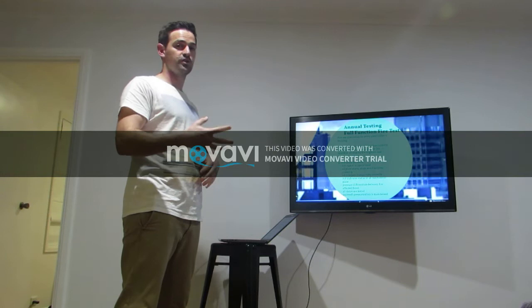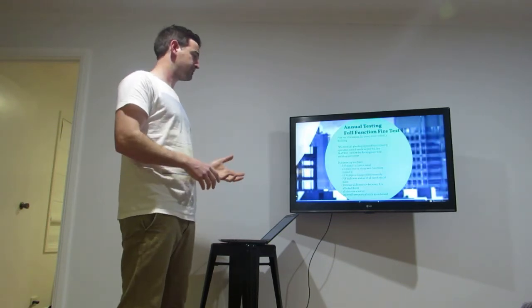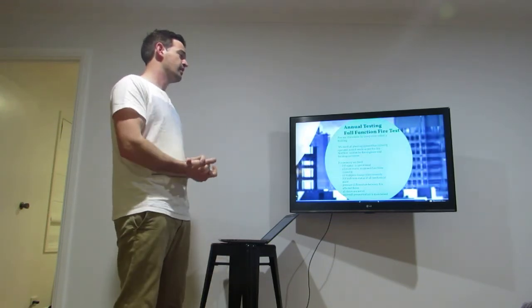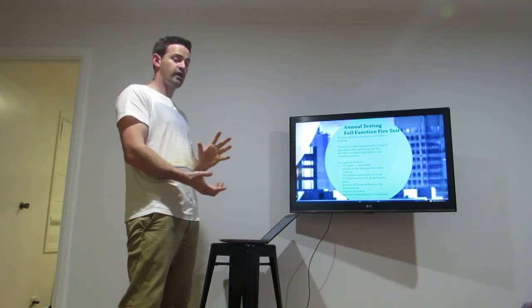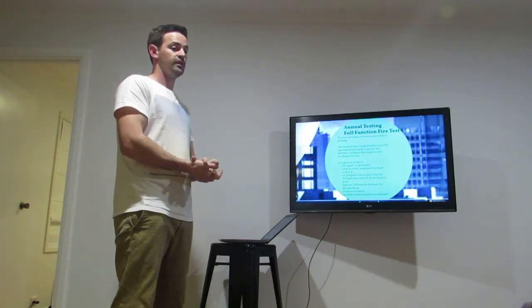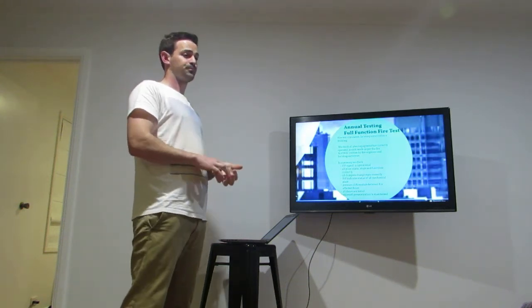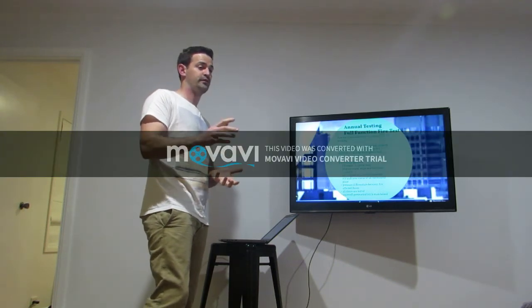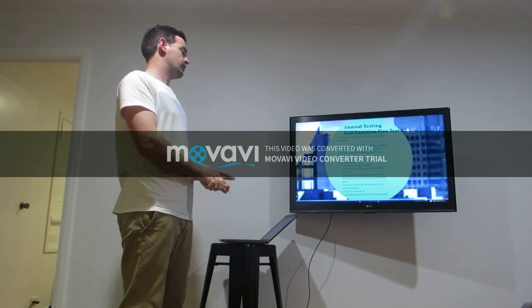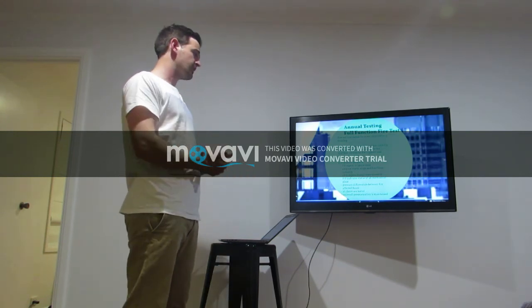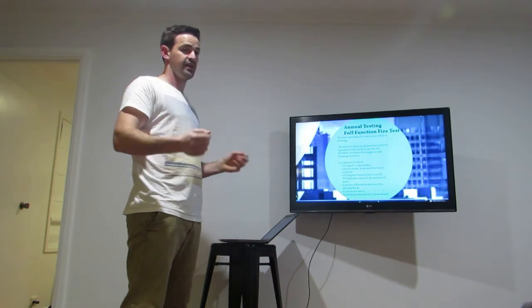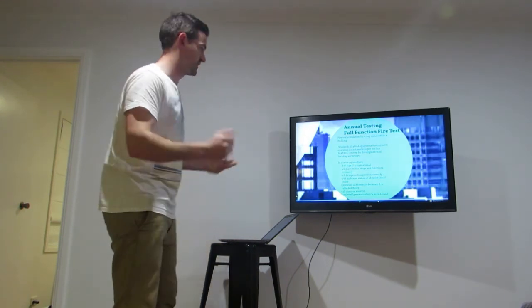The fire indication panel indicates the status of the mechanical plant. This is so firefighters can actually see what's going on, what's running, what's changing over. We also need to check pressure differentials between the fire floors and the non-fire floors. We need to be able to pressurize from 20 pascals to 50 pascals for the floor above a fire floor. We also need to check all doorways are clear and the latches spring open. We also check stairwell pressurization is carried out as previously discussed.